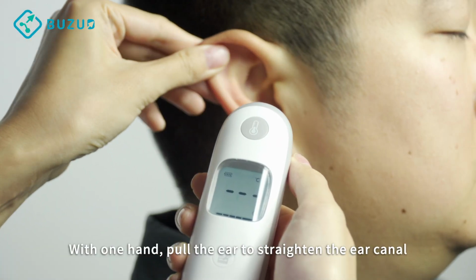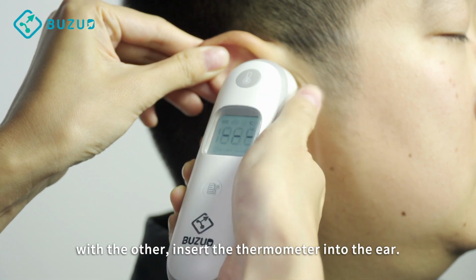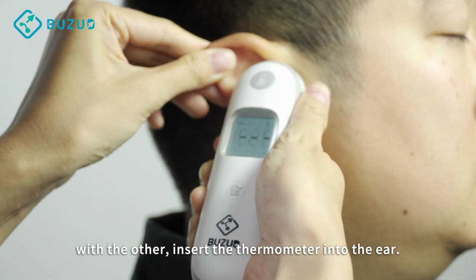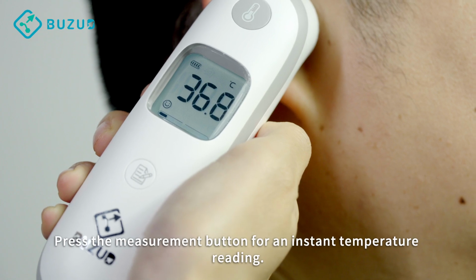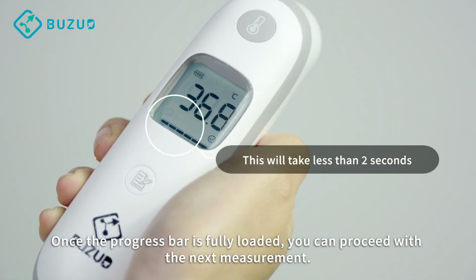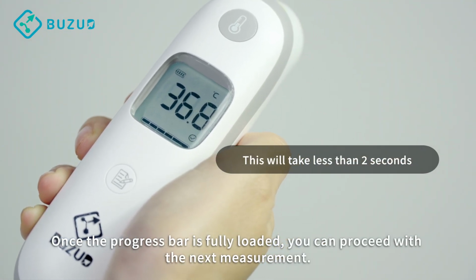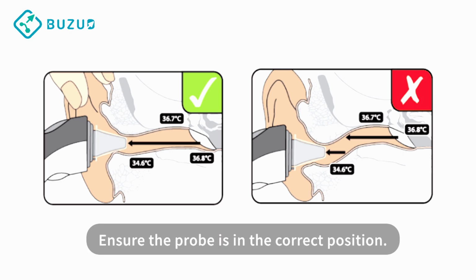With one hand, pull the ear upwards. With the other, insert the thermometer into the ear. Press the measurement button for an instant temperature reading. Once the progress bar is fully loaded, you can proceed with the next measurement. Please pay attention to the position of the probe.